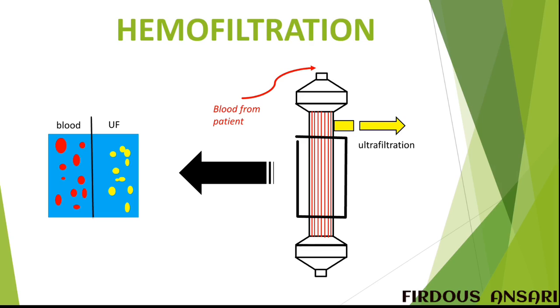Okay, so a large amount of blood volume is removed, and below, from here, the purified blood is added back to the patient's body. But because of this volume removal, a replacement fluid is added back after the hemofilter to maintain adequate volume status in the patient.